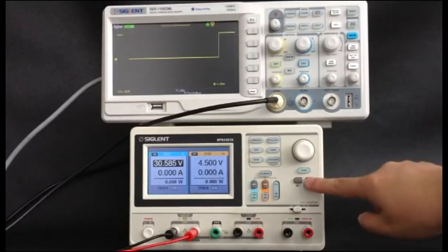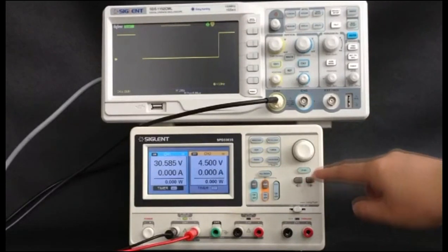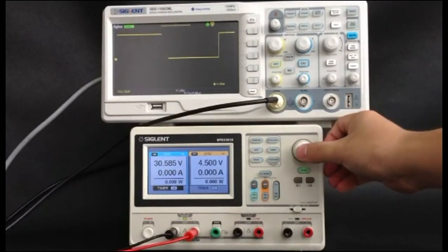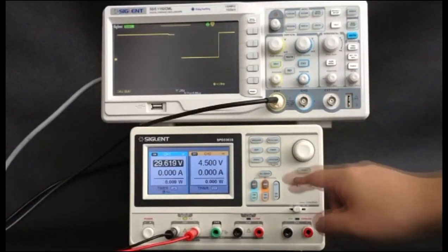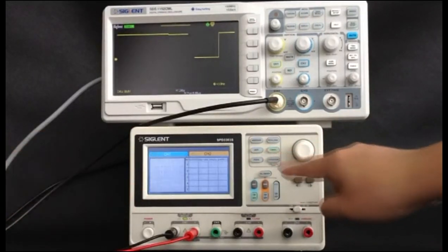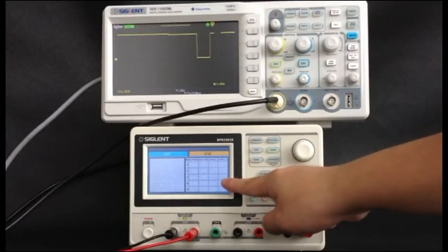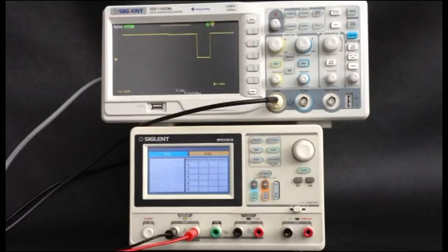Move cursor to timer menu by pressing the direction button. Revolve the multifunction knob to make the timer state to on. The output changes according to the value set by the timer output. Then send the signal to the oscilloscope.